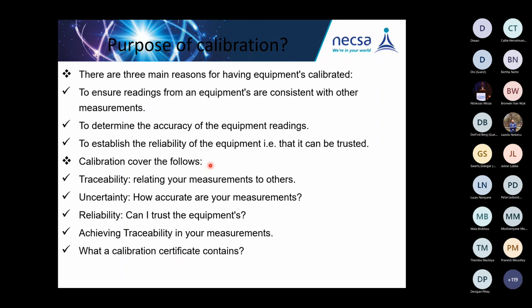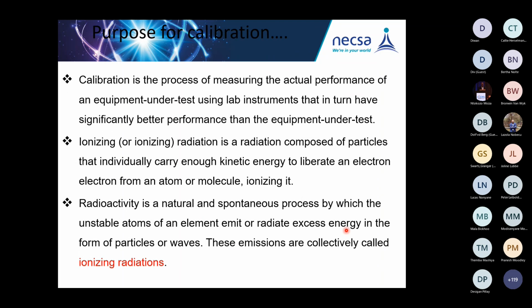And then the calibration covers the following: traceability, relating your measurements to others, which is the national measurement standard; uncertainty, how accurate your measurements are; reliability, can I trust this equipment; and achieving traceability in your measurement. What a calibration certificate contains, I will also put in at another end. I've got some certificates to present. I've already emailed them to Mr. Ditole, and I will ask him to load them after, or I can load them from my side.